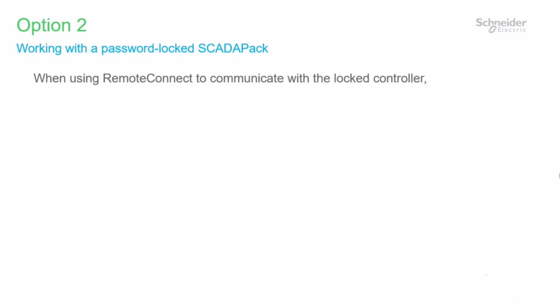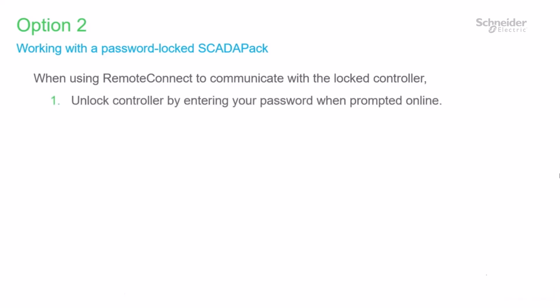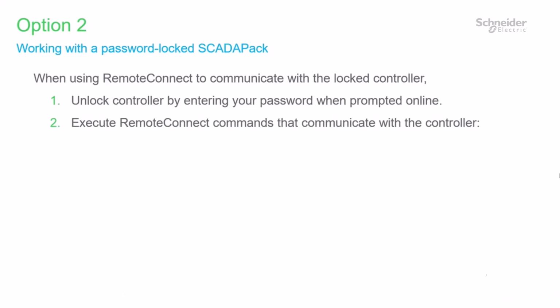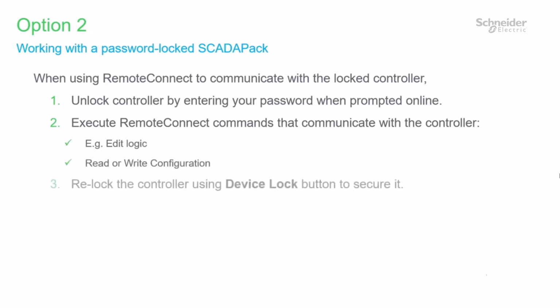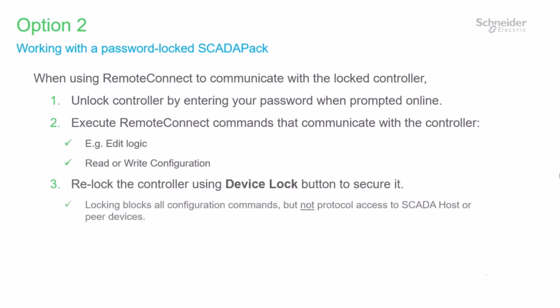Let's summarize how we work with a password-locked SCADAPack. Whenever you need to communicate with RemoteConnect and a locked controller, the first step is to unlock it. As soon as we go online, it will prompt us for that password. Then we use RemoteConnect to execute any commands, browse data, write configuration. Finally, we relock the controller using the device lock button to secure it. Note that the locking blocks all configuration commands, but not protocol access to the SCADA hosts or peer devices.